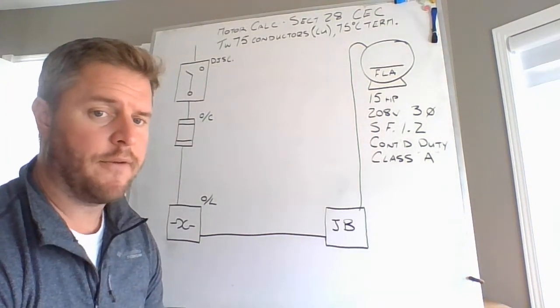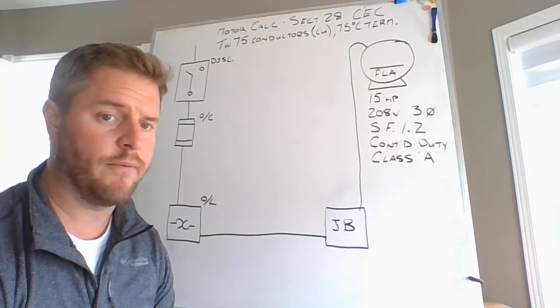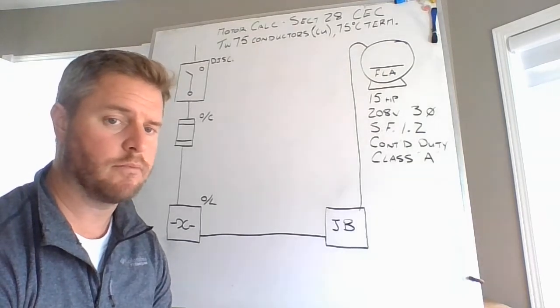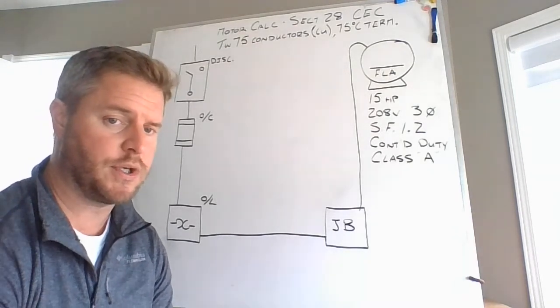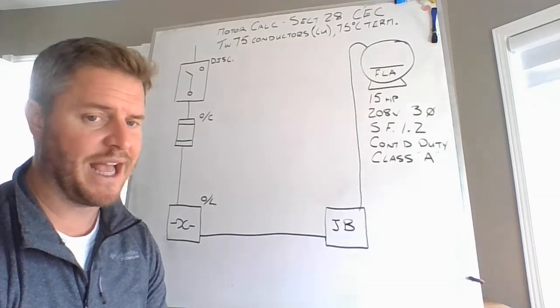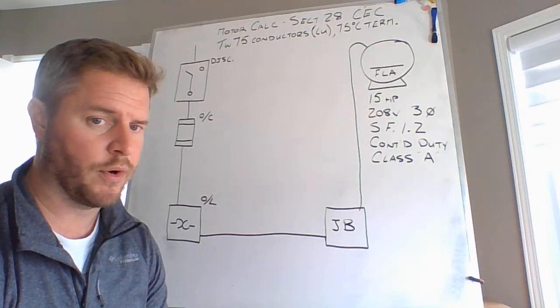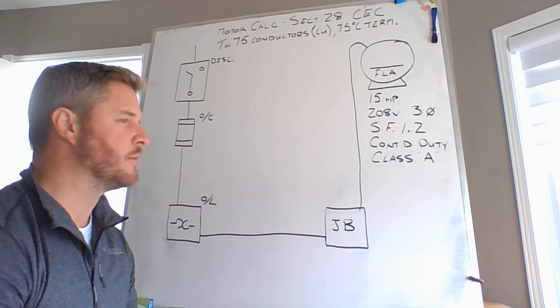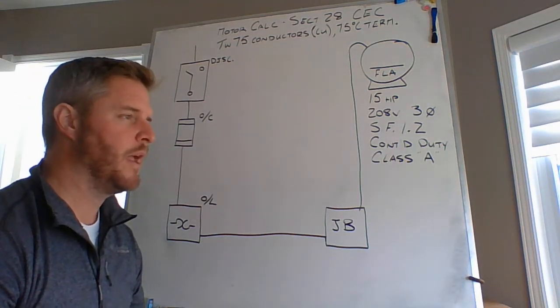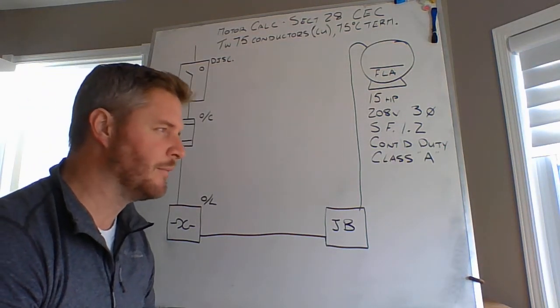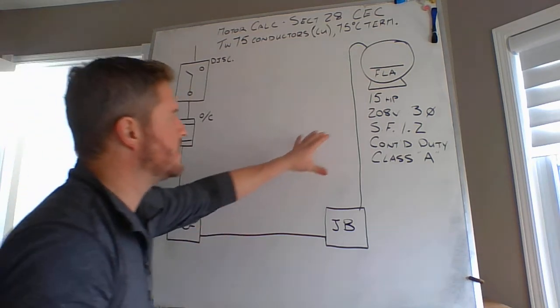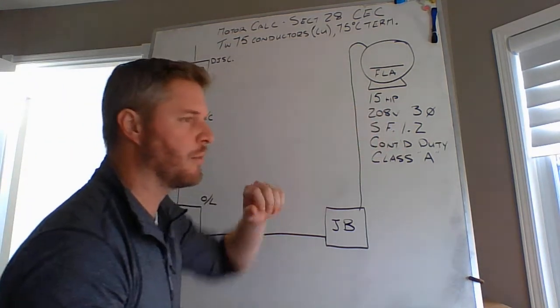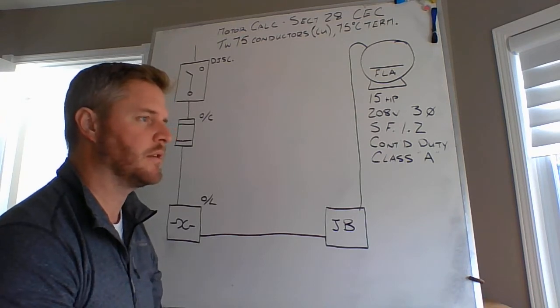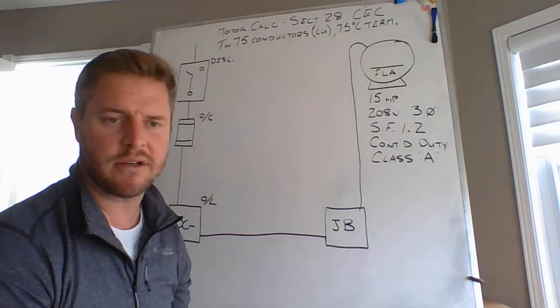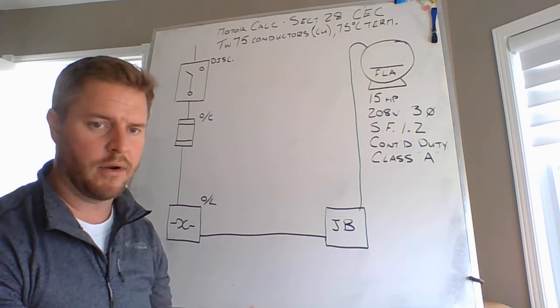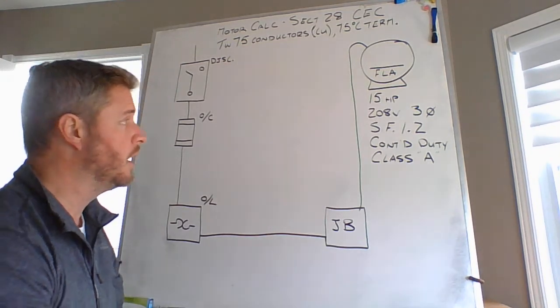So we are looking at a 15 horsepower, 208 volt, 3-phase motor with a service factor of 1.2, continuous duty, class A motor. Typically, these are going to be squirrel cage motors or auto starting motors, things like that. These are just standard 3-phase motors when we're looking for overcurrent protection and sizing our conductors, utilizing Section 28 to our capabilities so far.